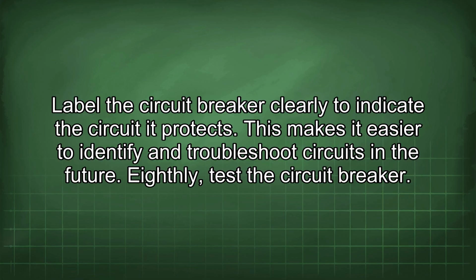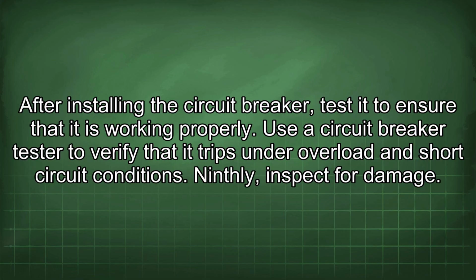Eighthly, test the circuit breaker. After installing the circuit breaker, test it to ensure that it is working properly. Use a circuit breaker tester to verify that it trips under overload and short circuit conditions.